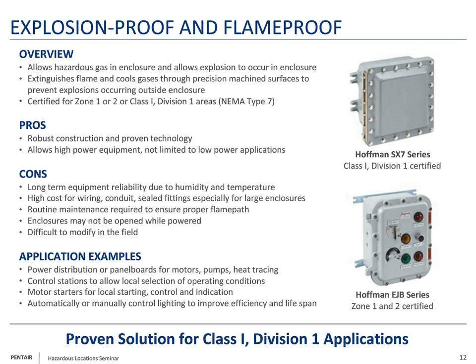So the pros: this is highly proven, very well adopted in the marketplace, very robust, and allows for high power equipment to be used, so it's not limited to low power applications. But there are some challenges associated with this type of solution. One is long-term equipment reliability, especially when it comes to heat and humidity. You see a lot of condensation management challenges with these types of enclosures. They trap the heat and the humidity within them, especially in large temperature swing environments, especially if you're near a coastal environment.